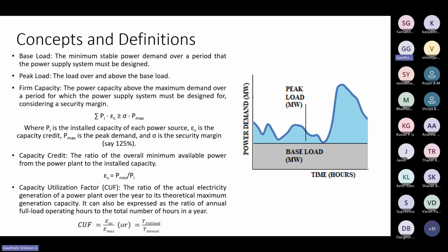So when planning the power supply for any city, you need to keep a few things in mind. One is the firm capacity. Let's say your demand is 100 megawatt, you need to ensure you're installing at least 125 megawatt, so about 25% overrating.